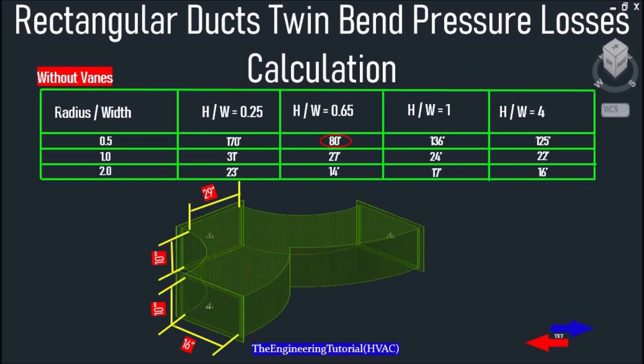We'll use this table for the rectangular duct twin bend or double elbow without vanes. If you divide the height of the right side of the double elbow by its width, that gives us 0.65. So we simply select an equivalent of 80 feet for the right side and 80 feet for the left side of our double elbow. If that ratio had come out to 1, we would have selected an equivalent of 136 feet; if it came out to 4, we would have selected 125 feet.